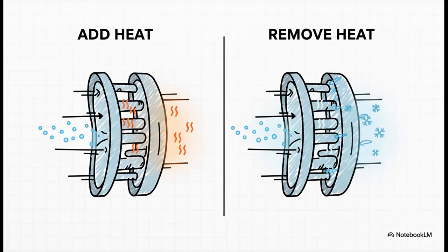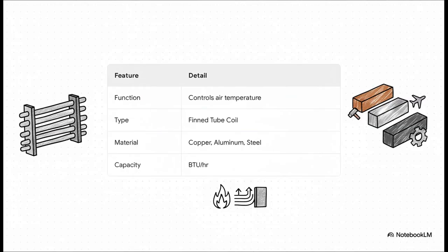Okay, after the fan, the air hits the coils. This is where the real temperature magic happens. You've got either hot water, chilled water, or some kind of refrigerant flowing through these super intricate coils, and their job is to either add heat to the air or pull heat out of it to get it to that perfect temperature. Now, the design of these coils is all about one thing: maximizing heat transfer.